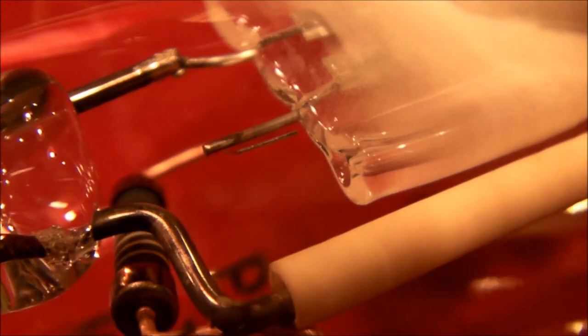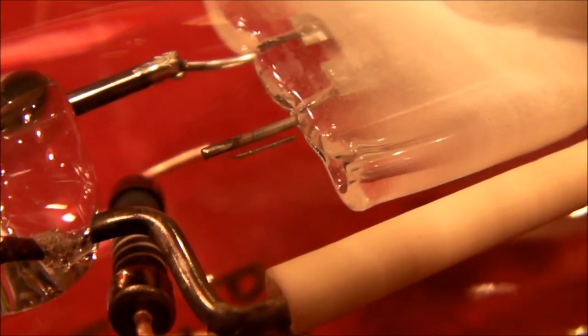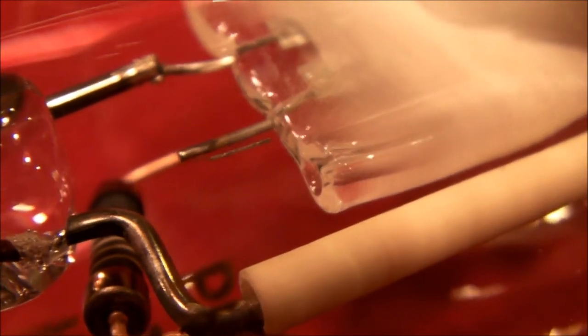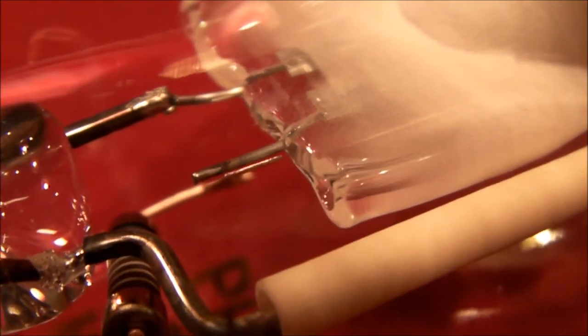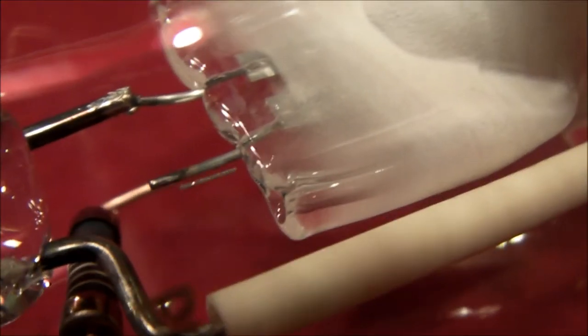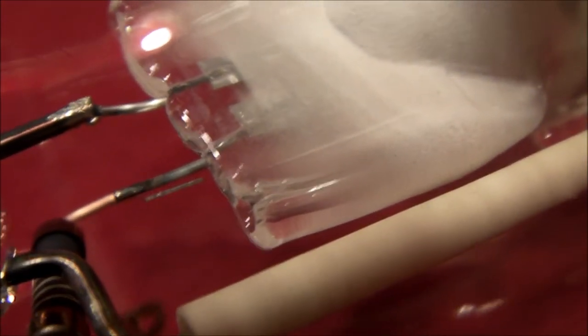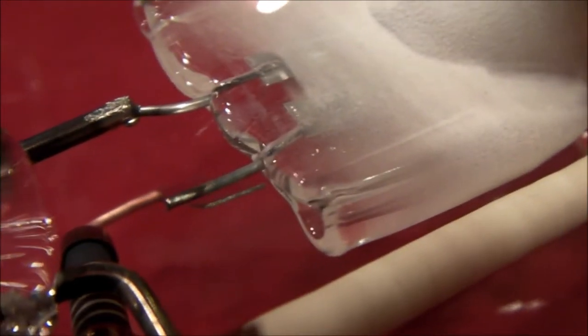Right there you can see there's a gap. The starting electrode and the bimetal are not touching, which is why the lamp won't start. The warmer the weather is, the closer the bimetal gets to that starting electrode.